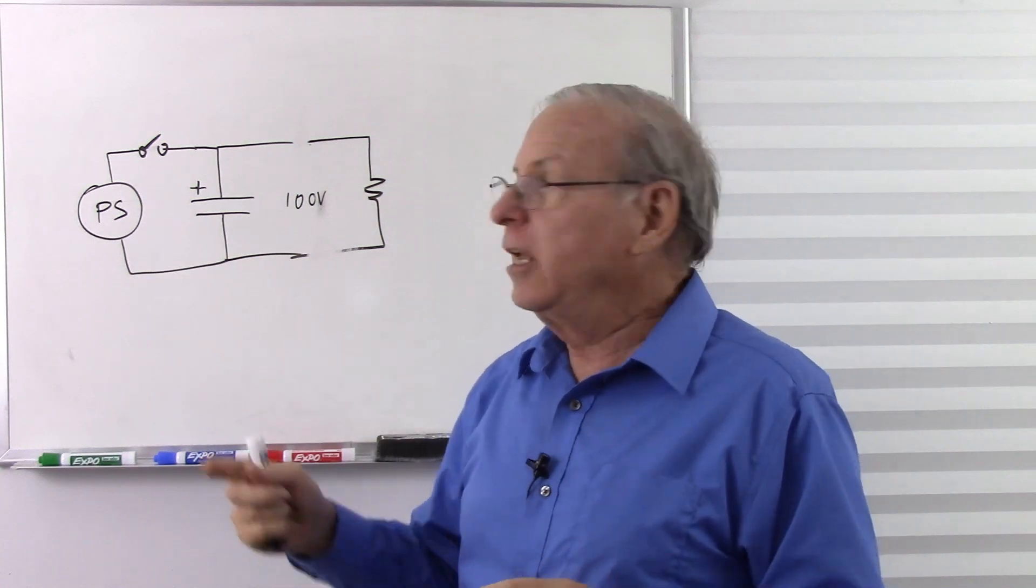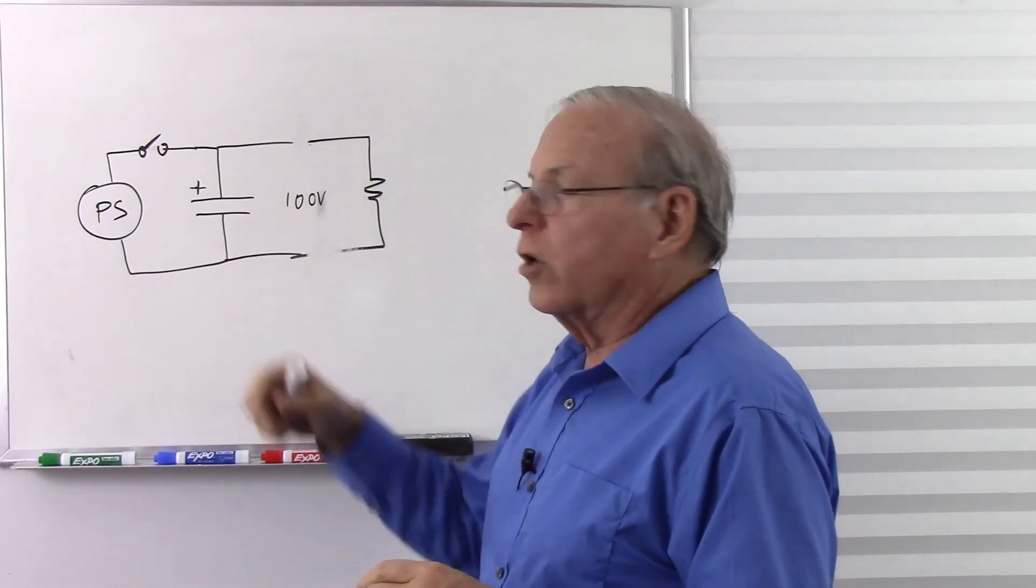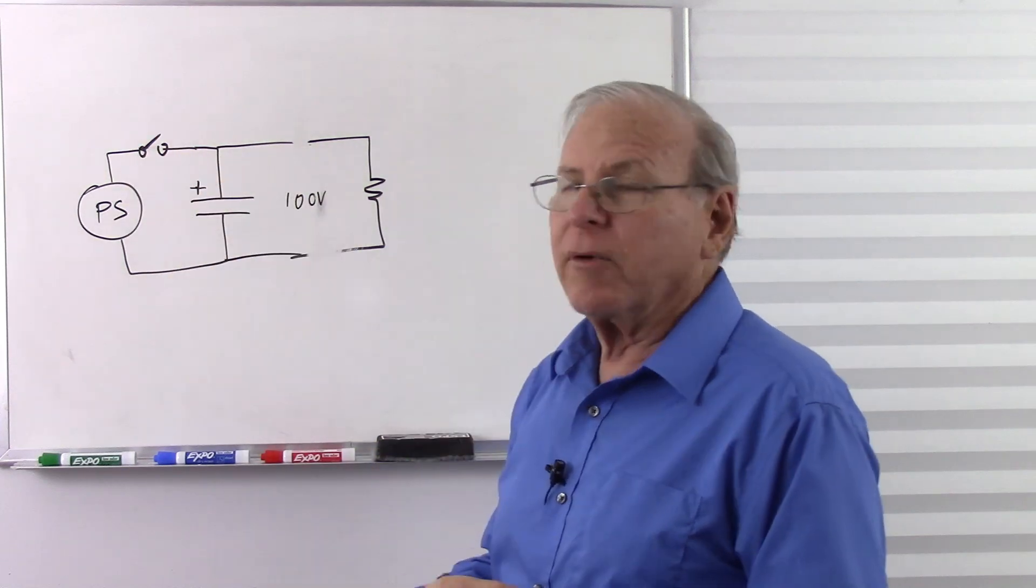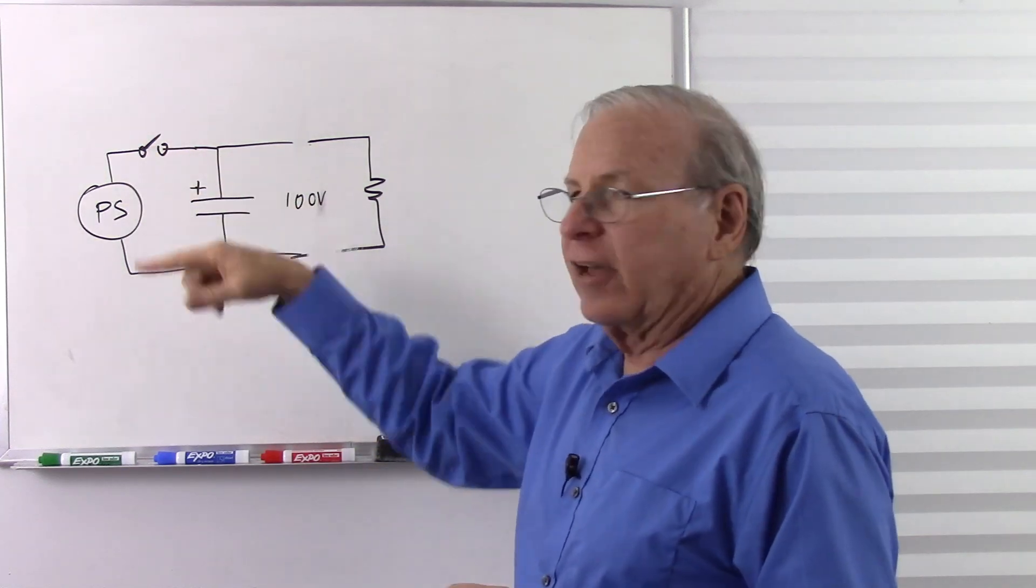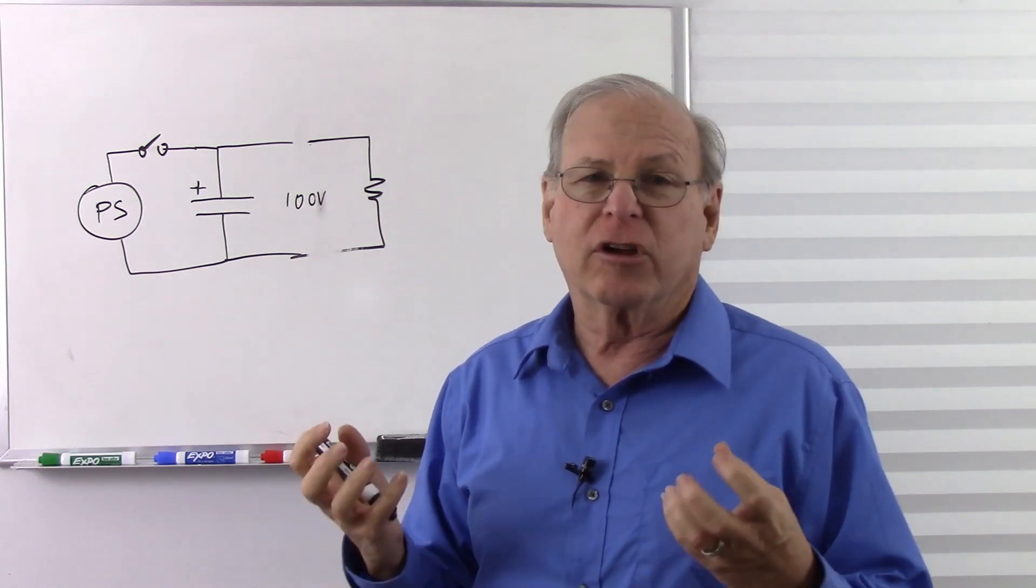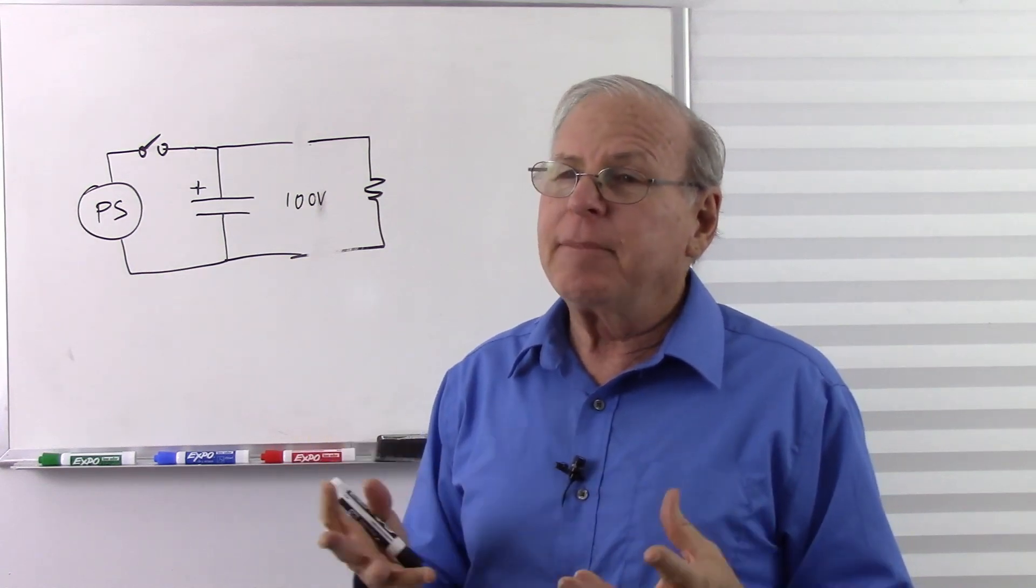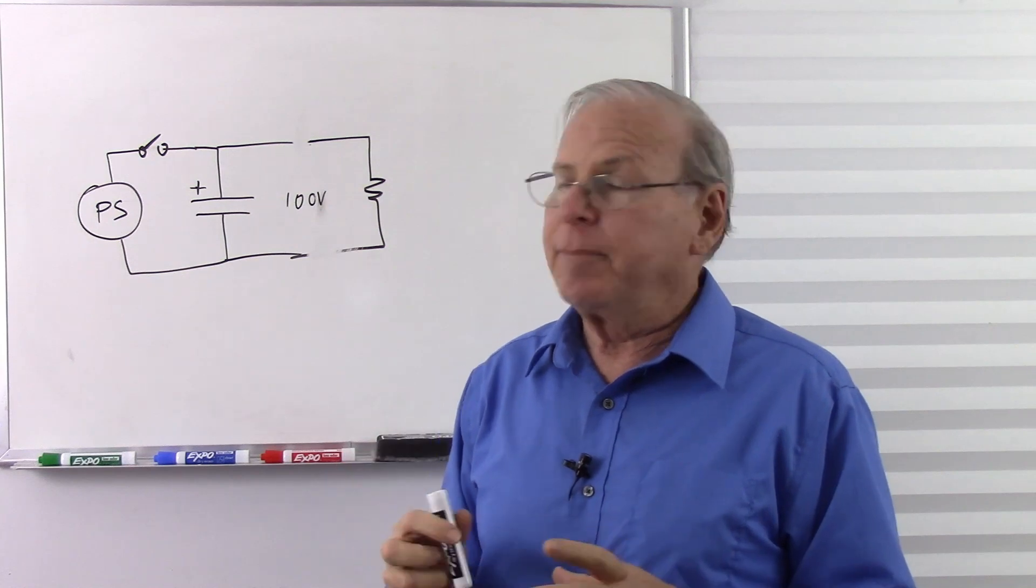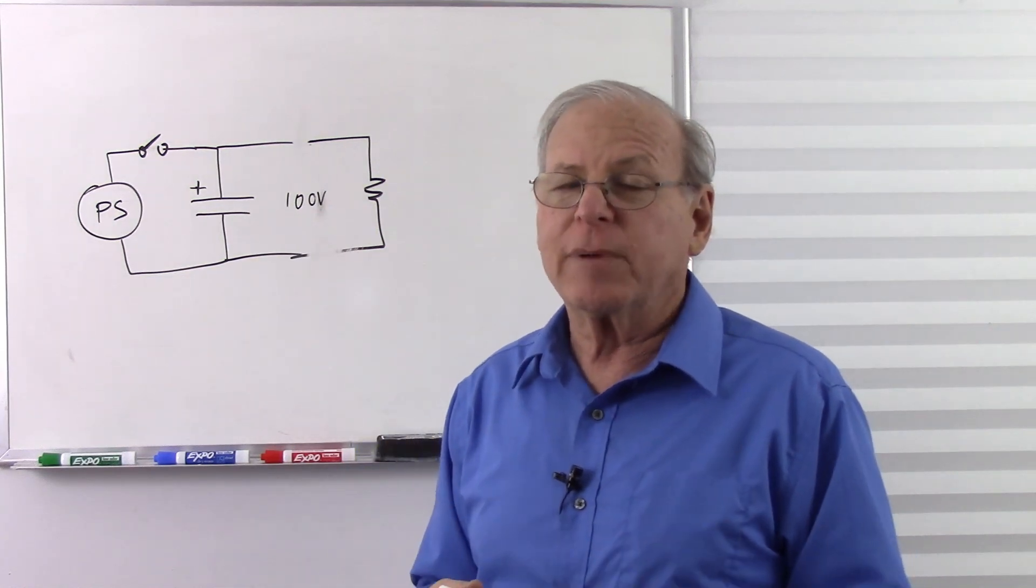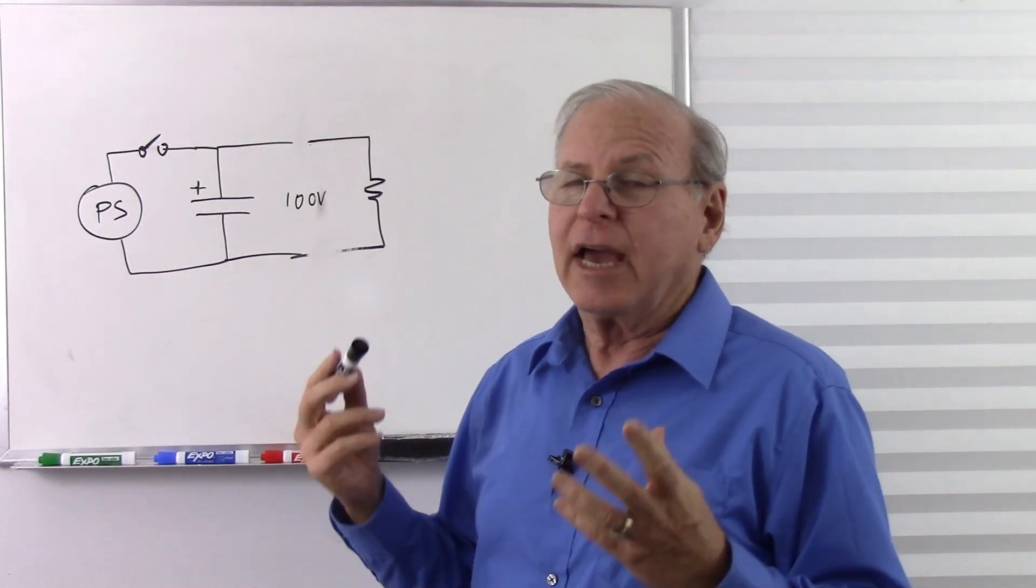And then we decide, oh, we need to do some work inside here. So we open up the power supply and start poking around in there. What do we have? We have a capacitor that's charged up to 100 volts. And it's probably a big capacitor, so it can store a lot of energy. And it can be dangerous. It can be deadly. People have been killed by charged capacitors in high voltage power supplies. So you have to keep that in mind.